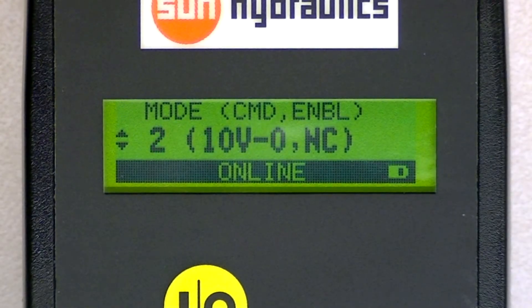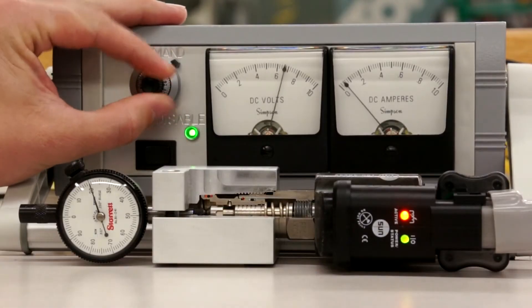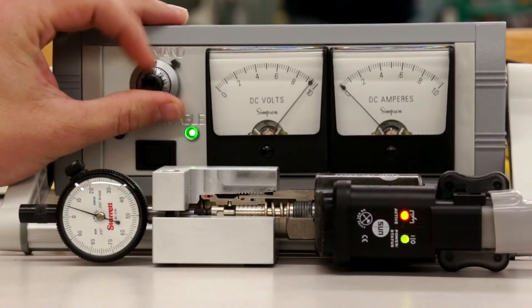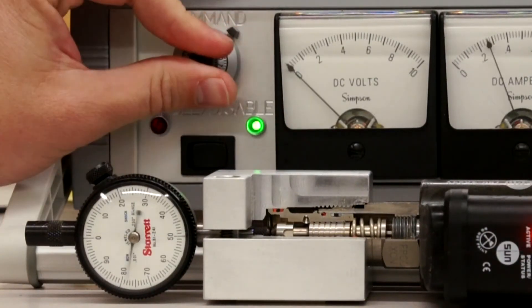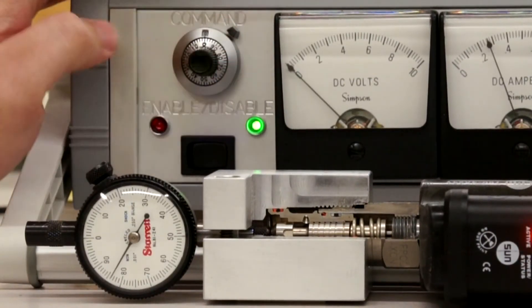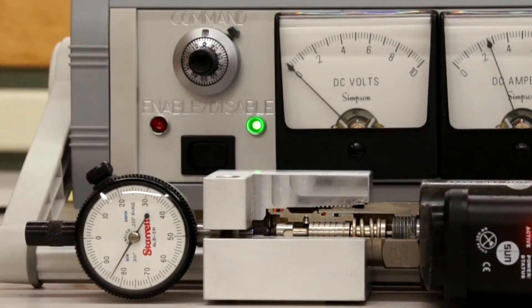Mode 2 is the inverse of mode 1, so now 0 volts will give you full current output. So now as you increase the voltage from 0 to 10 volts, the valve will close. 10 volts gives you the minimum output current and 0 volts gives you the maximum output current. Again, the enable is not connected.